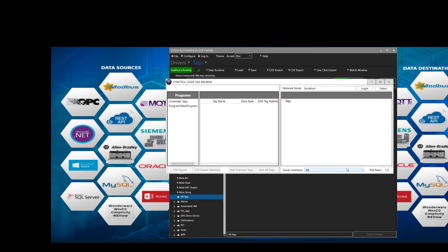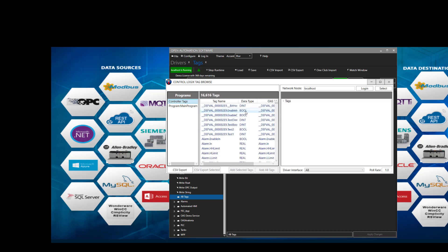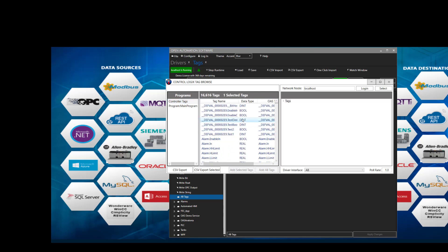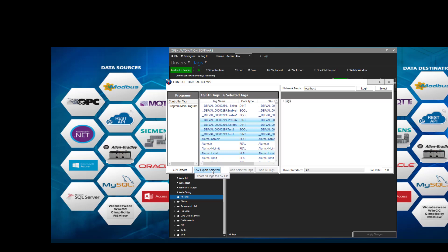Select the driver interface for the PLC you want to connect to, and then select the program that you want to import. We'll see here a list of all the AB Logix tags in the PLC. We can select individual tags, holding Shift-Select or Ctrl-Select to select individual ones. From here we can do a CSV export of all the tags or the selected tags, and that can be used later to import into OAS.